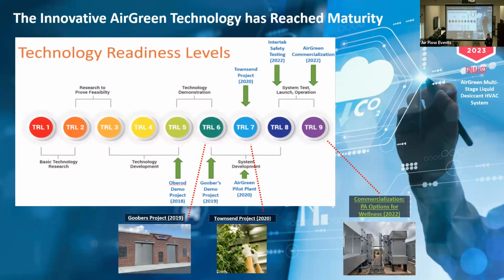They have moisture removal ratings of, if we use the dehumidification ratings that people that put in-room dehumidifiers in, like Quest units, use, a residential standard of 80 degrees Fahrenheit, 60% relative humidity. And they give their numbers in terms of pints per day. Our 2,000 CFM units as constructed today will do at those levels about 2,200 pints per day. And the 3,000 CFM unit will do about 3,300. We've just made some changes. We think that number is going to go up a little bit. But like most dehumidification systems, you work with the load that's presented.